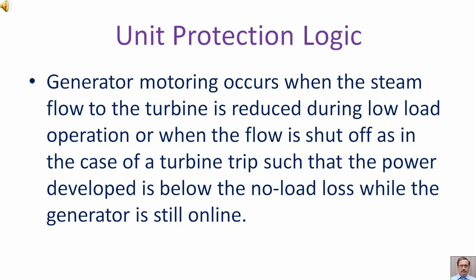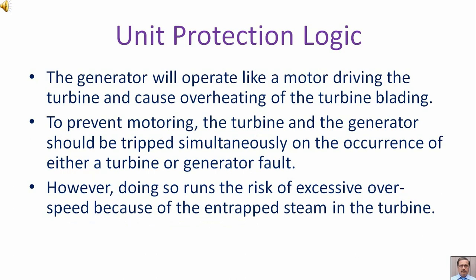Generator motoring occurs when the steam flow to the turbine is reduced during low load operation, or when the flow is shut off as in a turbine trip, such that the power developed is below the no-load loss while the generator is still online. The generator will then operate like a motor driving the turbine and cause overheating of the turbine blading. To prevent motoring, the turbine and generator should be tripped simultaneously on the occurrence of either a turbine or generator fault. However, doing so runs the risk of excessive overspeed because of the entrapped steam in the turbine.